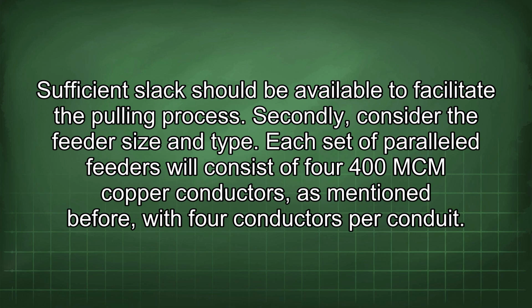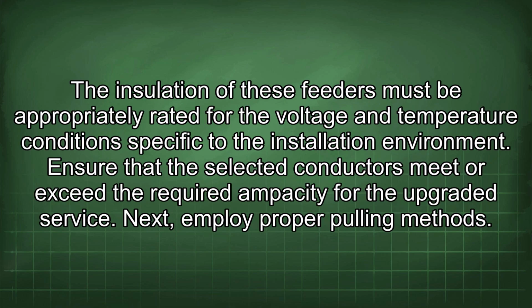Secondly, consider the feeder size and type. Each set of parallel feeders will consist of 400 mcm copper conductors, as mentioned before, with 4 conductors per conduit. The insulation of these feeders must be appropriately rated for the voltage and temperature conditions specific to the installation environment. Ensure that the selected conductors meet or exceed the required ampacity for the upgraded service.